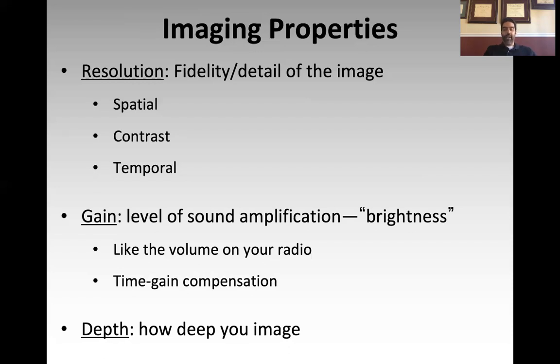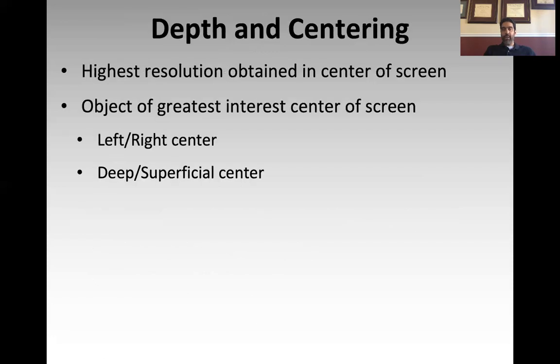And finally, depth — depth refers to how deep you are imaging. The thing to remember is that the highest resolution of imaging on the machines we have is going to be of the object that is dead center on the screen — both up-down and left-right dead center. So when you're scanning, you want to place the object of greatest interest in the center of the screen. The left-right centering is accomplished by sliding the probe along the axis, and the deep-superficial centering is accomplished by adjusting your depth setting on the machine. When we talk about individual ultrasonographic modalities, we'll discuss where to center your imaging based on what you're looking at.